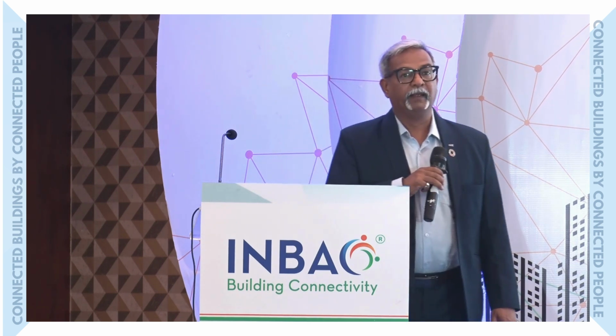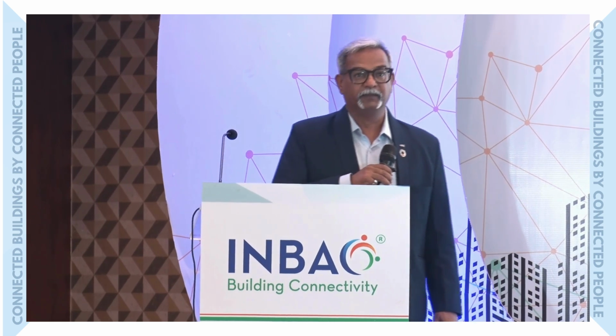Please continue your question. You showed one sensor, an occupancy sensor and a temperature sensor, right? Yes, that is an infrared sensor. So what happens in unitary products, like split units, high wall mounted units, or cassette units, by law of nature the cold air tends to settle down and the hot air rises up. So the machine ends up sensing the return air temperature, which is at a higher level and not indicative of the room temperature.